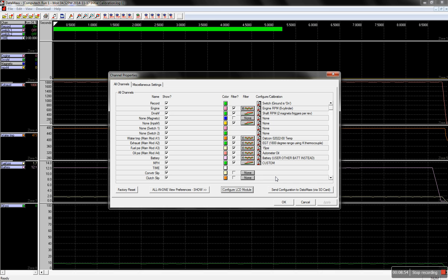Now keep in mind that the calibration information that we just changed right here, it is actually not saving it so much to the SD card, but it is actually saving it to the Datamax data logger itself. So the Datamax data logger, every time it records a log file, it has that little calibration at the beginning of it. So it doesn't matter which SD card you use, as long as it's one of ours, or which computer you save the log file to, it will always have this custom information. So what we want to do now is go ahead and send the calibration back.